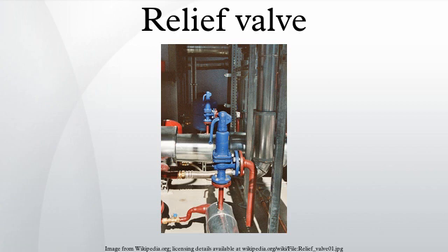In other cases, equipment must be protected against being subjected to an internal vacuum that is lower than the equipment can withstand. In such cases, vacuum relief valves are used to open at a predetermined low pressure limit and to admit air or an inert gas into the equipment so as to control the amount of vacuum.